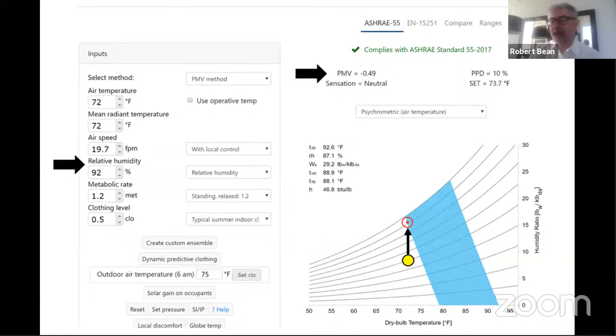We can be in compliance with the standard, but we can't sustain such high humidities, otherwise we'll create mold and moisture problems. So even though controlling humidity can bring a space into compliance, there could be building science issues related to that—it's not necessarily always good to raise the humidity in the space.